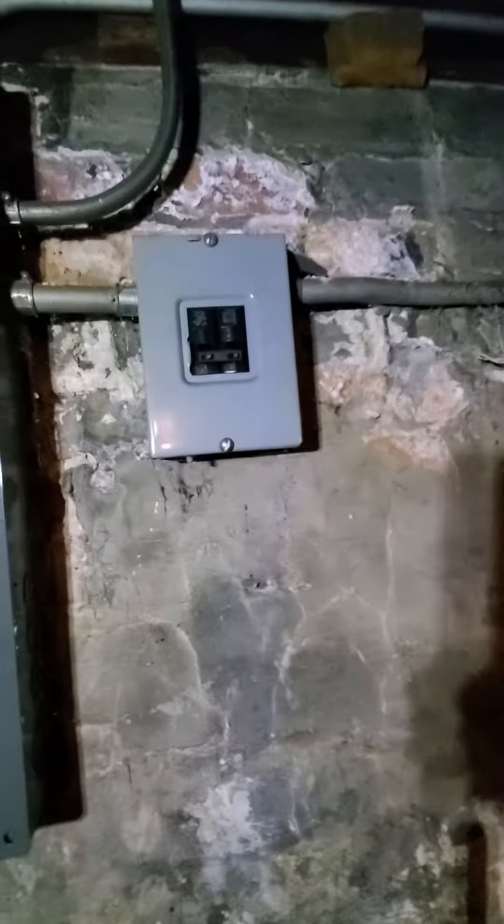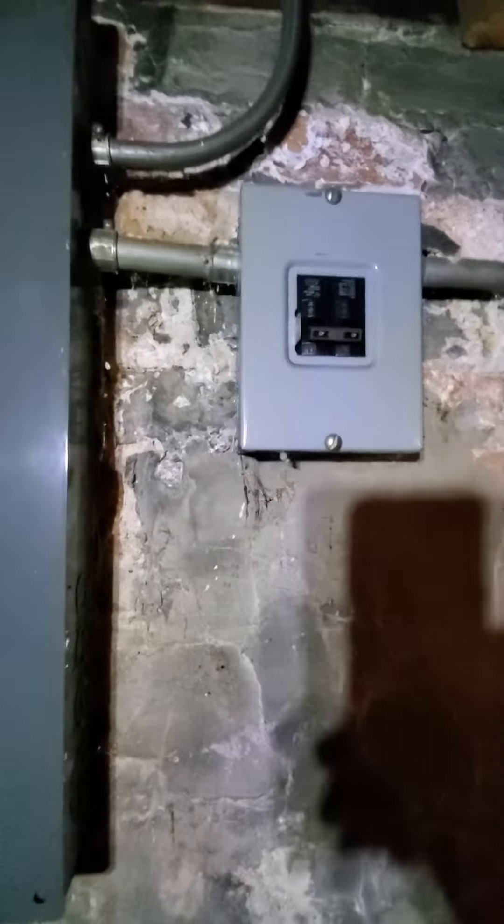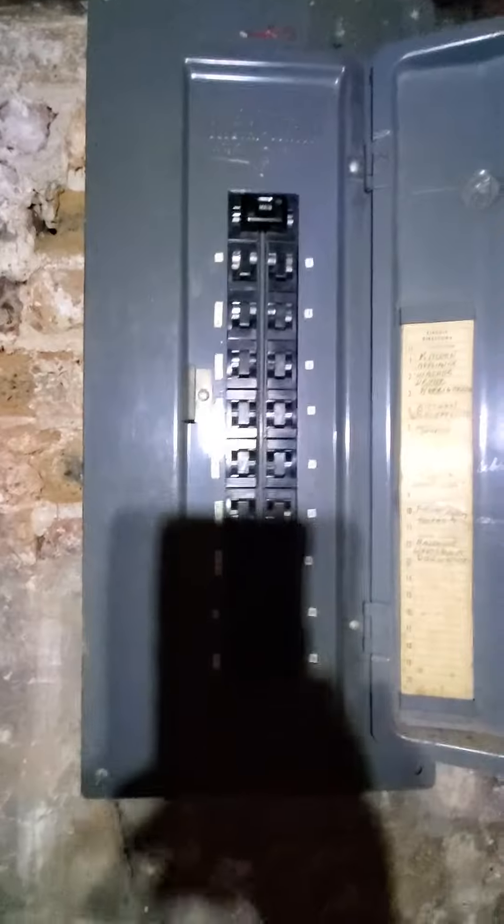Your breaker box is right back here. It's a Pushmatic Bulldog. It does look like we've added a fuse disconnect here from our previous job — 40 amps, double pole. I did grab some snaps of that, so it should be good on that end as well.